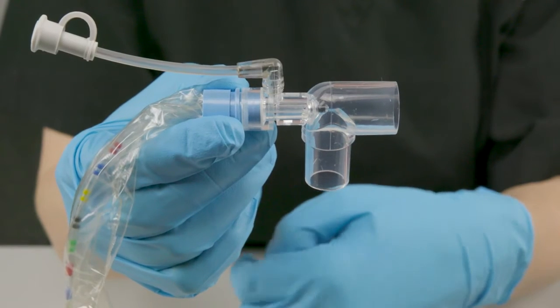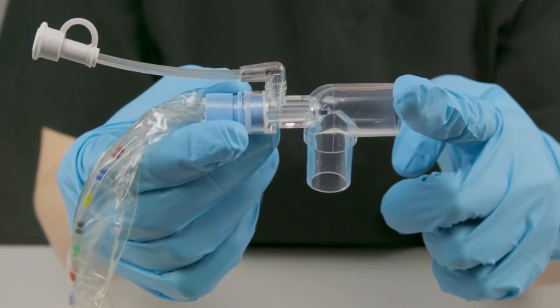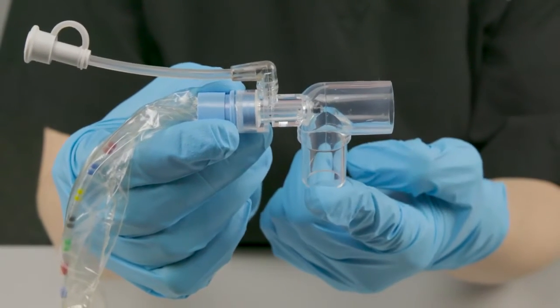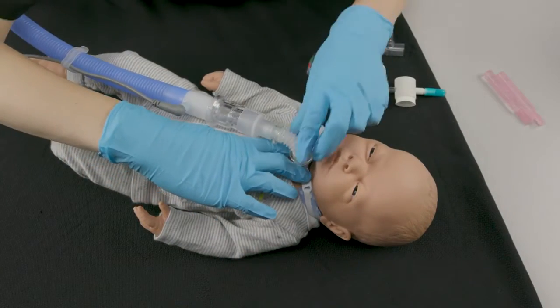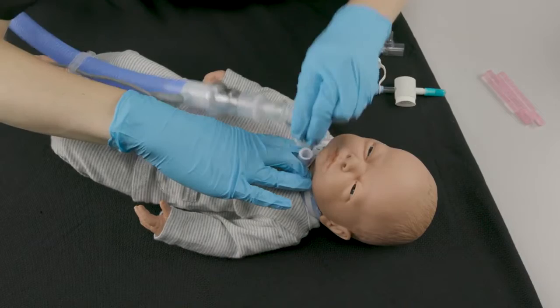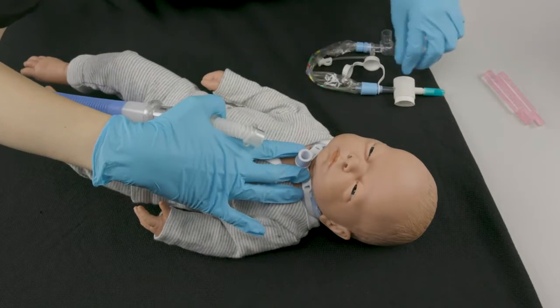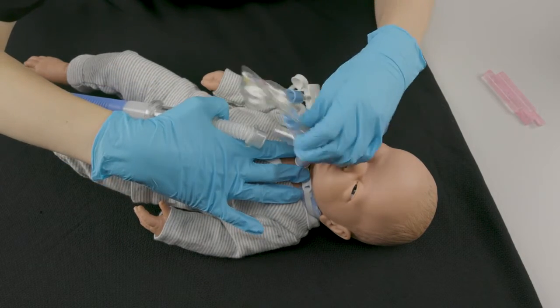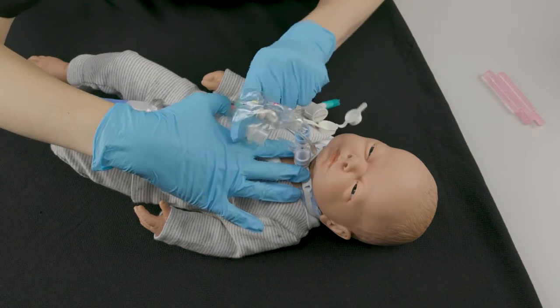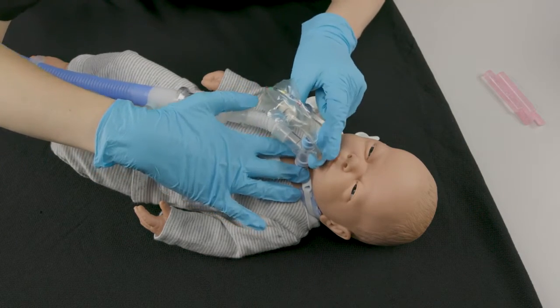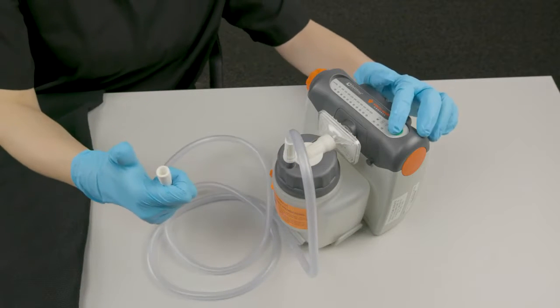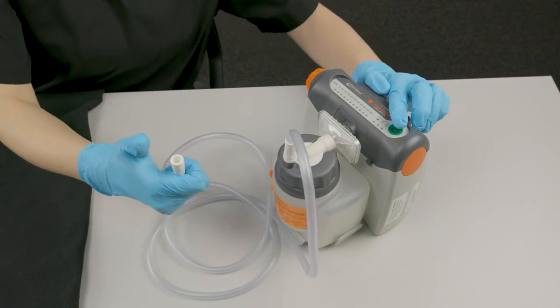The larger end of the attached adapter connects to the trach. The smaller end connects to the circuit. Disconnect the patient from the ventilator circuit and quickly connect the adapter to the trach tube and then the circuit to the adapter. Turn the suction machine on and check for safe suction pressure.